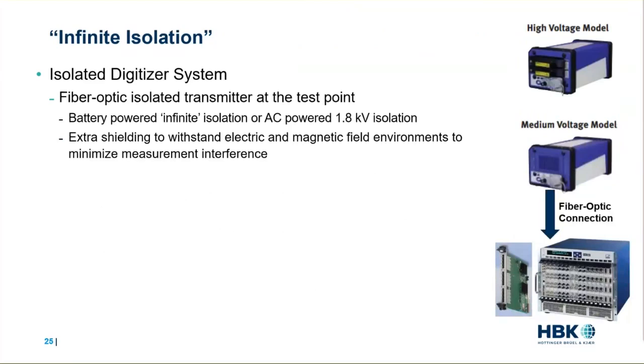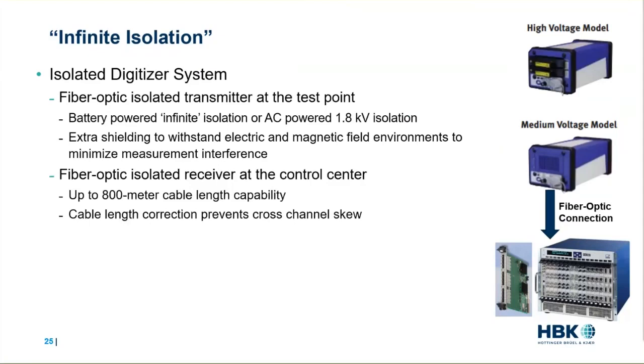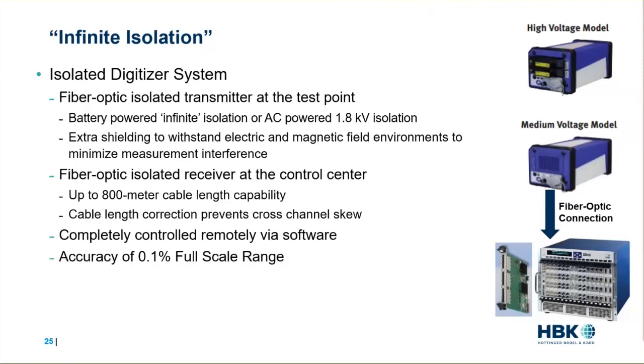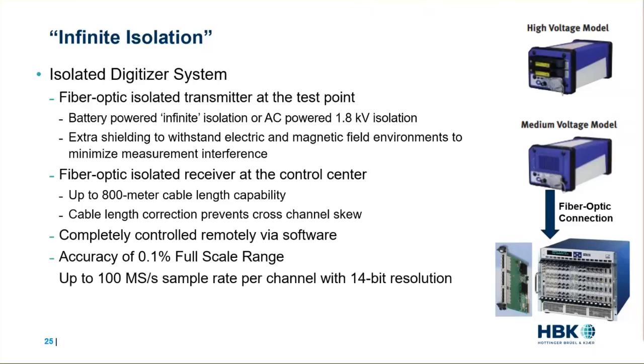There's even extra shielding to withstand electric and magnetic field environments to minimize measurement interference. And then you have a fiber optic isolated receiver, which is at the control center and at the mainframe. You can have up to 800 meters of cable length, so quite a distance from the lab. But even if you have different transmitters at different locations with different cable lengths, there's no need to be concerned, because the cable length correction prevents cross-channel skew, and that's done automatically. The whole system is completely controlled remotely via software and provides an accuracy of 0.1% full-scale range. The nice thing here is that you have up to 100 million samples per second per channel with 14 bits of resolution.